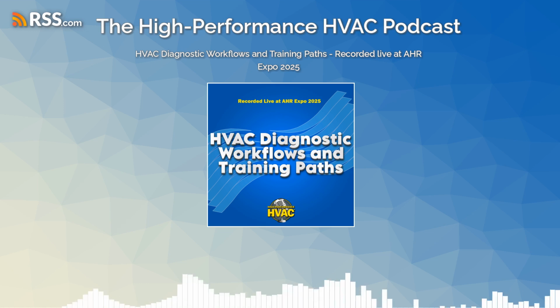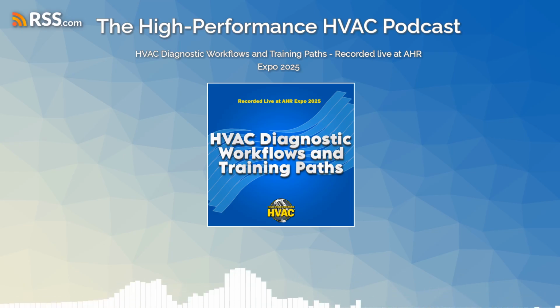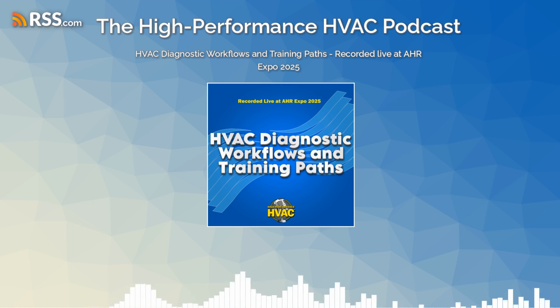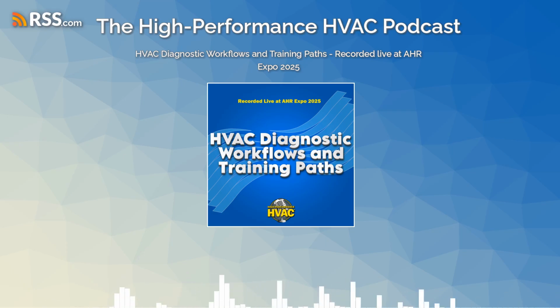Absolutely. I remember when I first learned static pressure - I actually told this story at the symposium a few days ago - when I first learned how to measure static pressure, you don't really learn what it means and what the individual measurements mean, what is good, what is bad, and why is it bad. One example is, if you're looking at total external static, you might actually have a problem on the supply side and the return side, but the problems balance each other out, and all you're looking at is total external static - you might miss what's going on with the system.